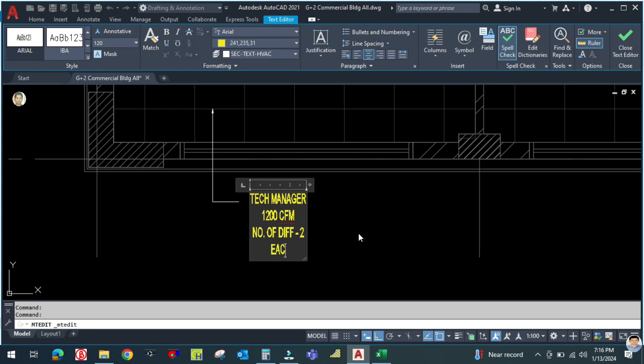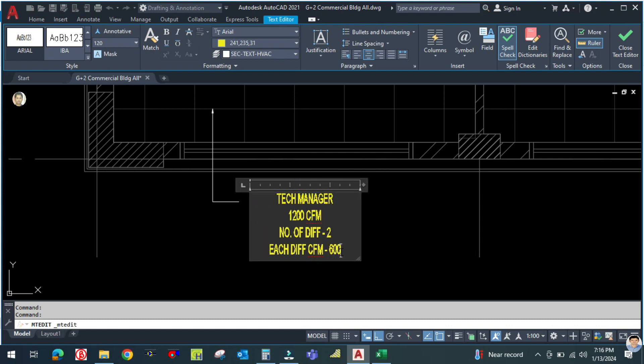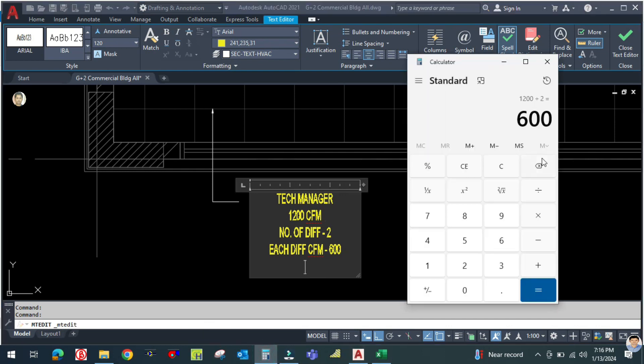Each diffuser CFM is equal to 600. The diffuser size can be selected from this. The formula is Q equals A times V — the area of the diffuser equals airflow divided by velocity.